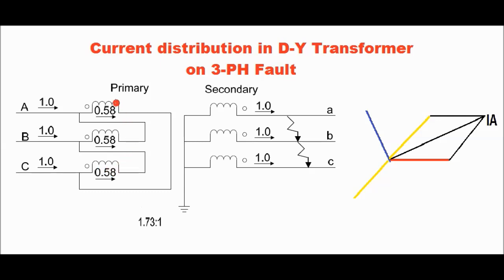Due to the flow of 0.58 ampere in each phase winding, the line current will be root 3 times the phase current. So the line current will be 1 ampere for the red, yellow and blue phase respectively. This is the fault current distribution for the delta-star transformer for a three-phase fault.